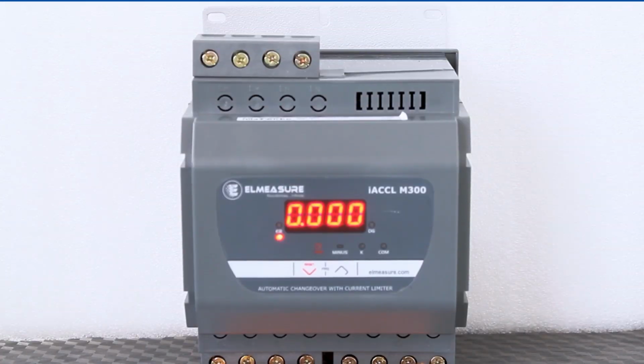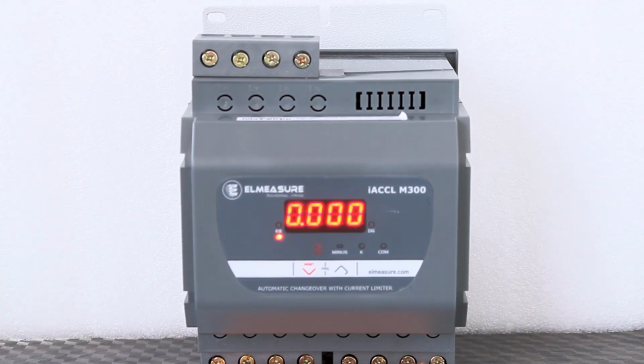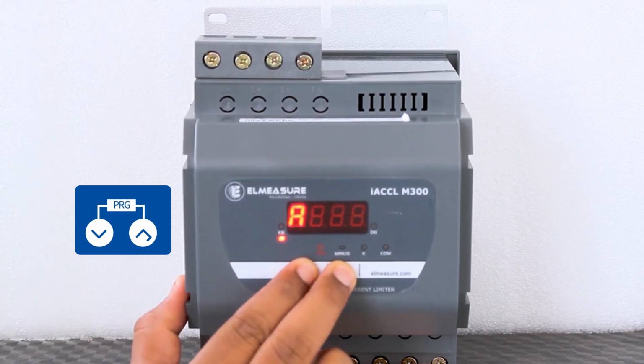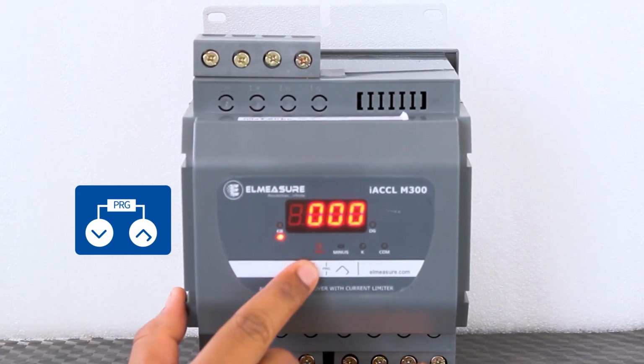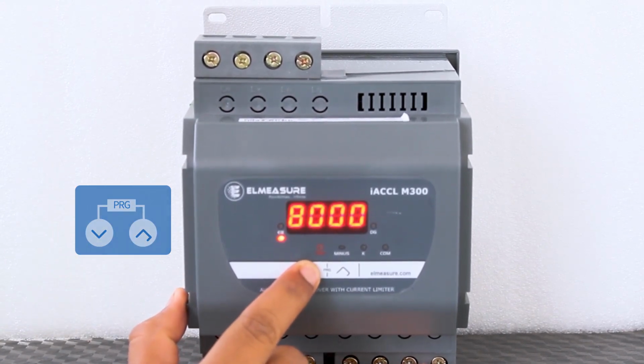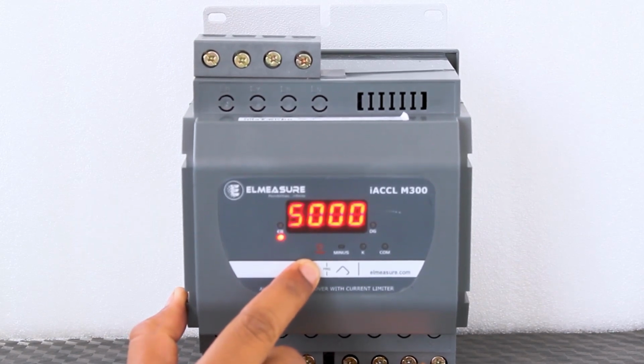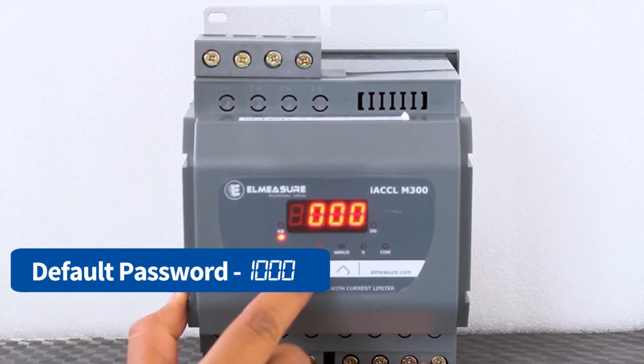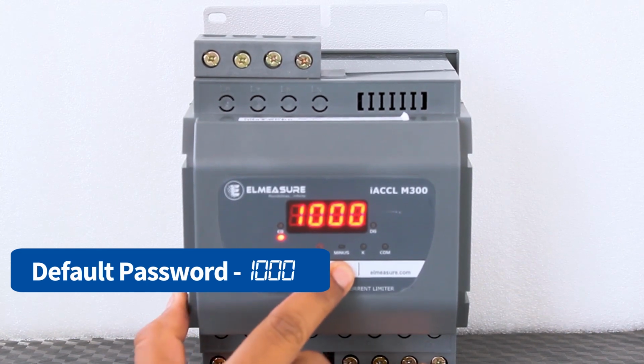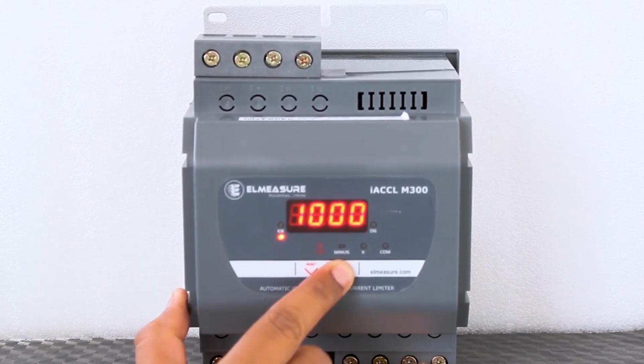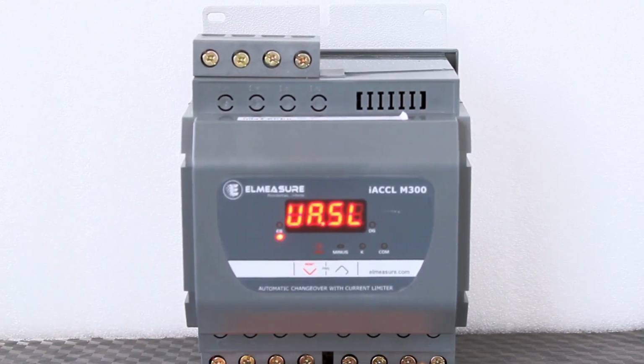Let's see how to configure the IACCL M300. Once you power on the meter, press both these buttons at the same time. This initiates the meter's configuration mode, and asks you to enter the device's passcode. The default factory set passcode is 1000. Set this code using the scroll down key and press the right enter key. The programming mode of the meter is now active.